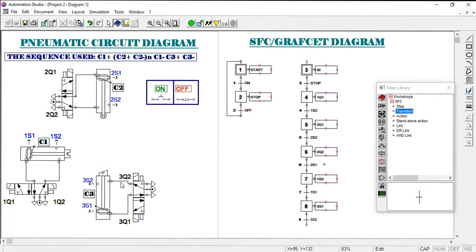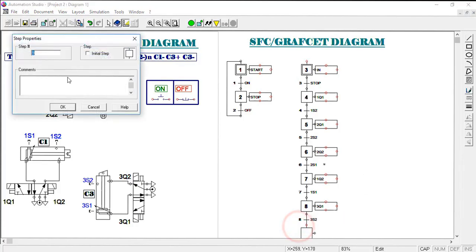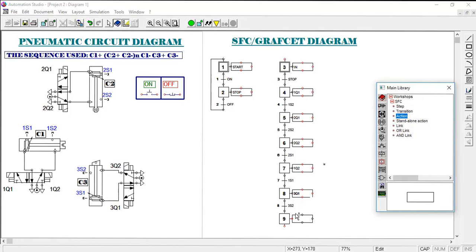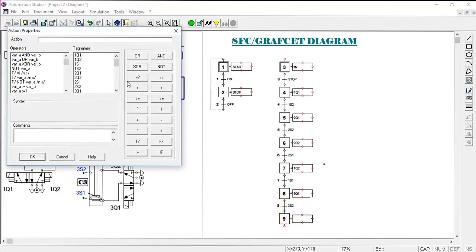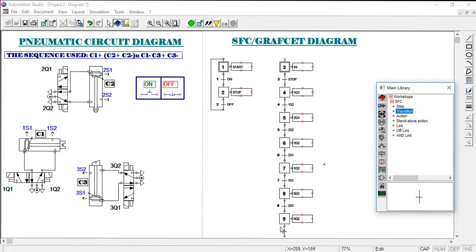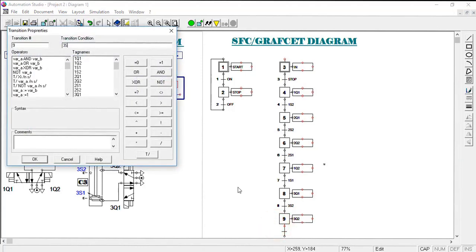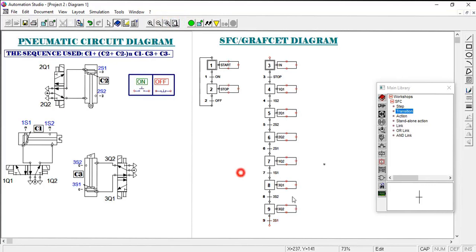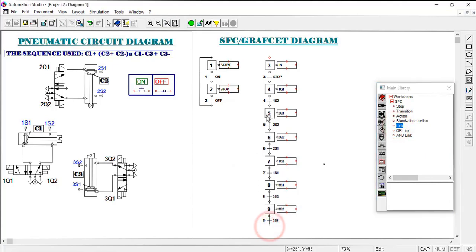When sensor 3S2 is triggered, the next step activates solenoid 3Q2 to retract the third cylinder back to its initial position. The final transition is 3S1, which detects the cylinder returning home. We then link from this final transition back to the initial step, completing the cyclic SFC program.